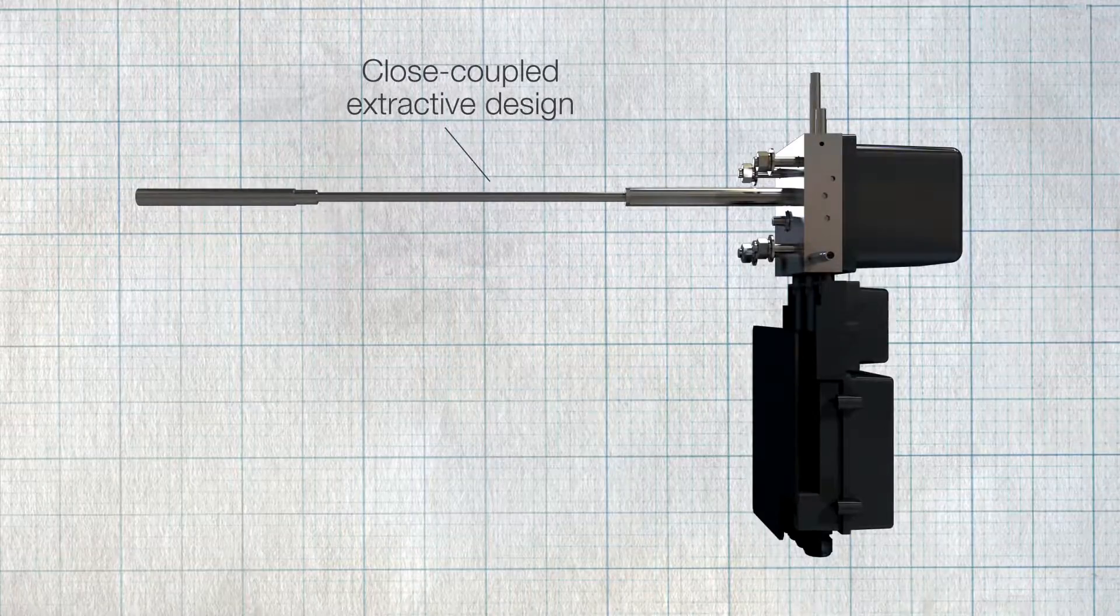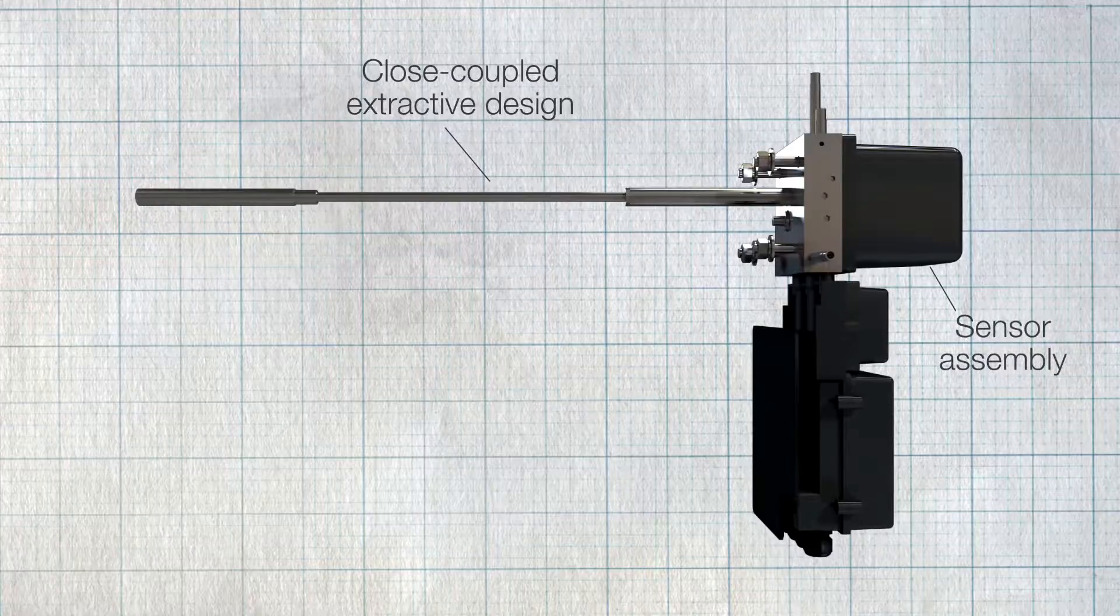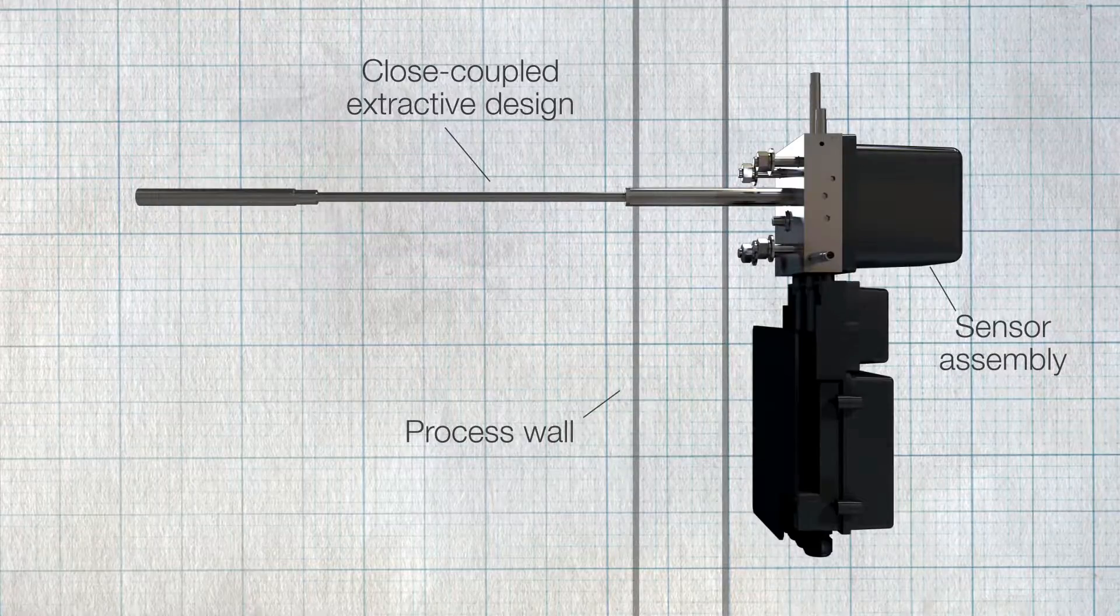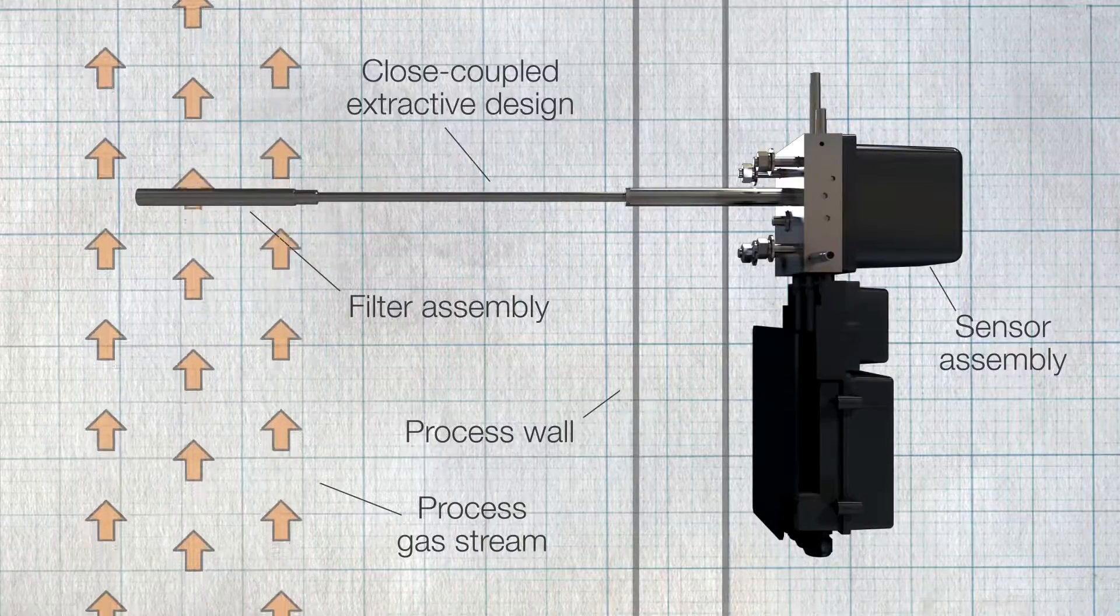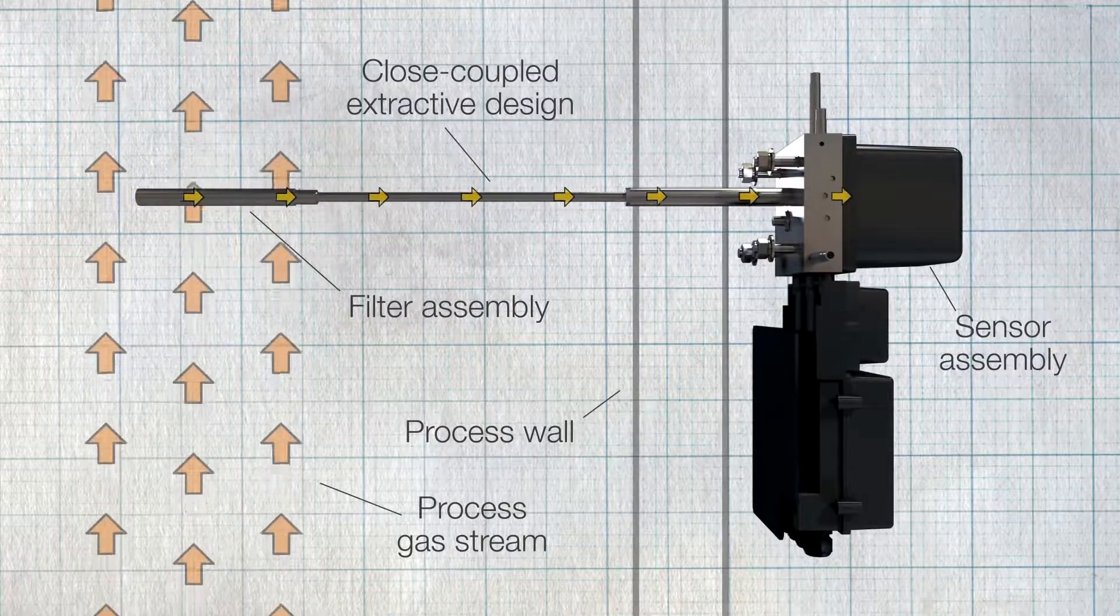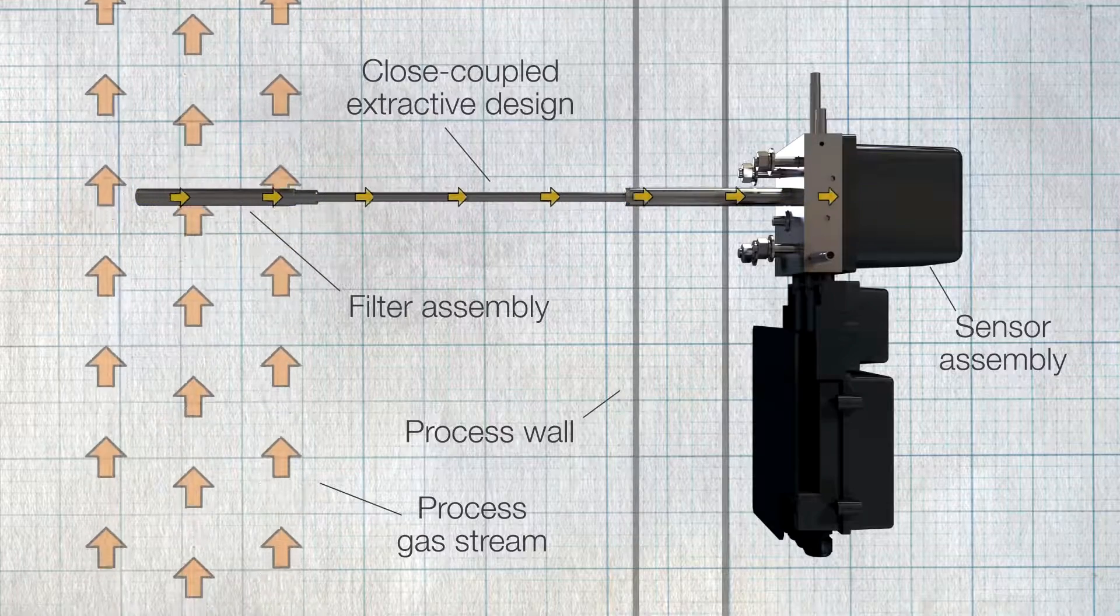Featuring a close-coupled extractive design, the AZ-40 uses a sensor assembly mounted on the process wall, with the probe and filter assembly extending into the process gas stream. The sample is extracted from the process and fed through the sensor head using an air-powered ejector.